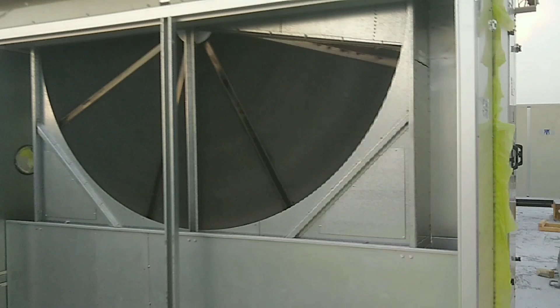For the heat recovery wheel, this is another system we already installed here. This unit, the center unit, is the heat recovery wheel. We already installed this. The same thing is here and here. The return air will pass through the heat recovery wheel. The wheel will rotate, and the cold exhaust air will strike this wheel, and the energy will be recovered from the cold air, and the wheel will cool down.